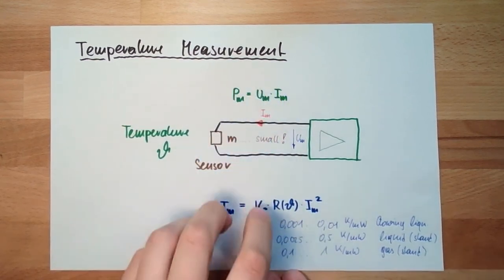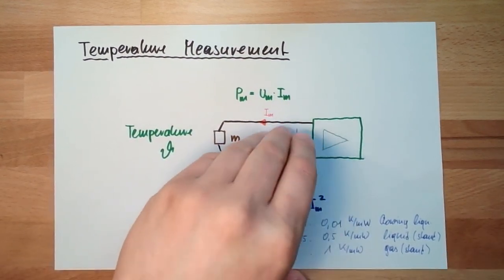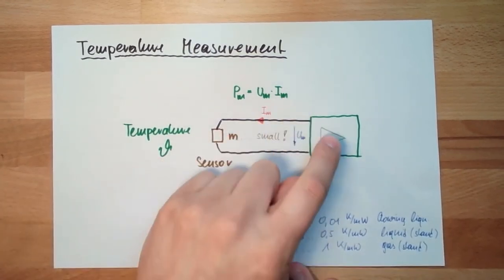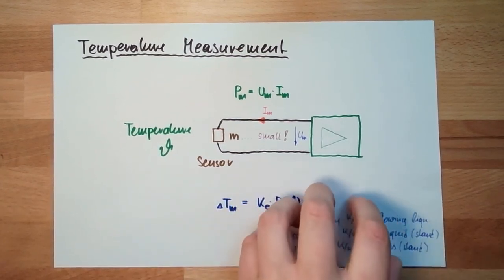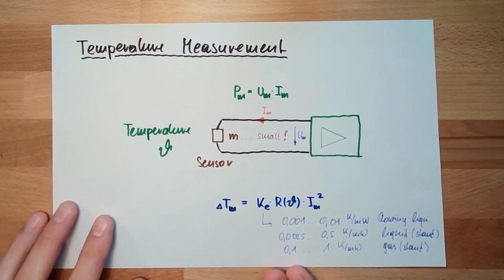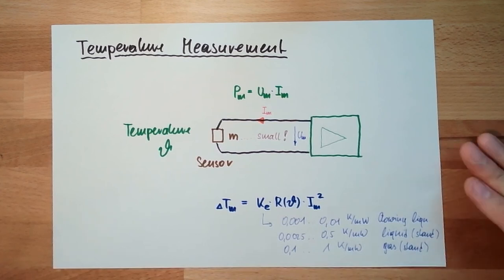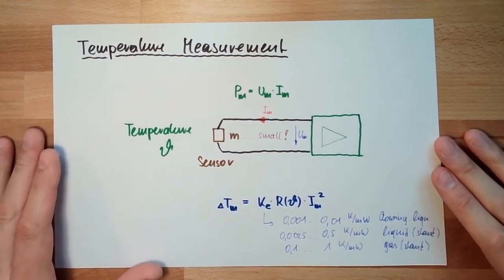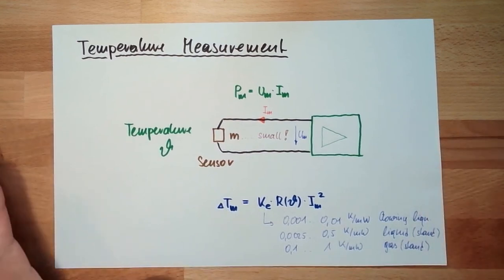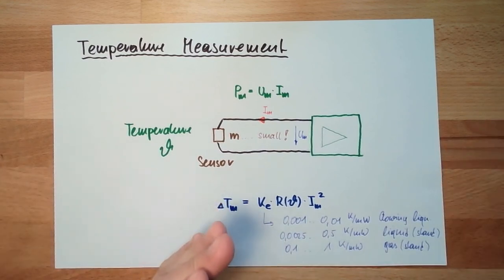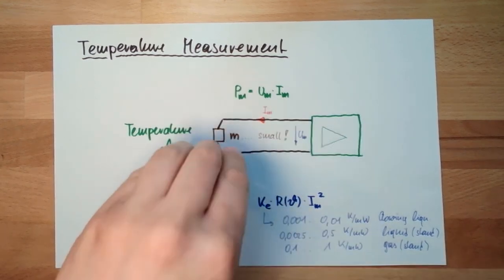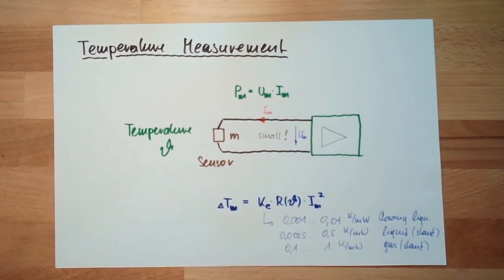So these two things, the mass of the sensor, which shall be small to influence less, and of course, the measurement current shall also be small. But for really accurate measurements, I can calculate this out. So these are systematic errors of my temperature measurement. So this is temperature measurement and the common errors which I'm handling here. Self-warming, and of course, the mass of the sensor, which needs to be brought to the same temperature. Because we really measured the temperature of the sensor and not the temperature we're interested in.